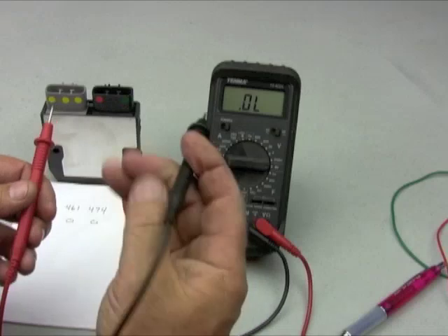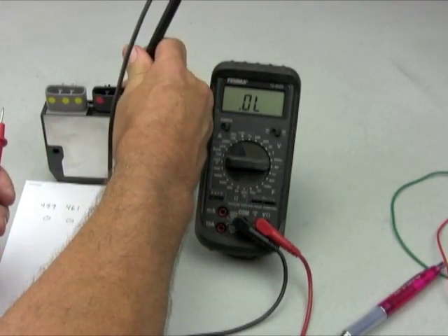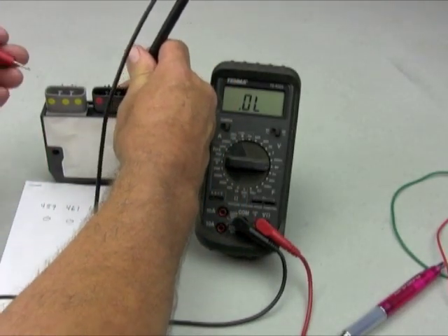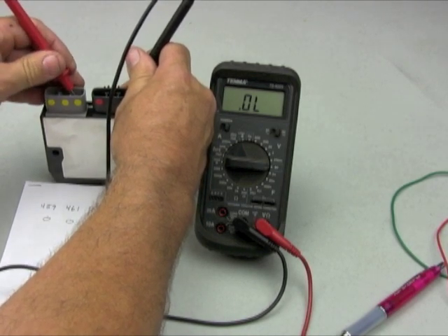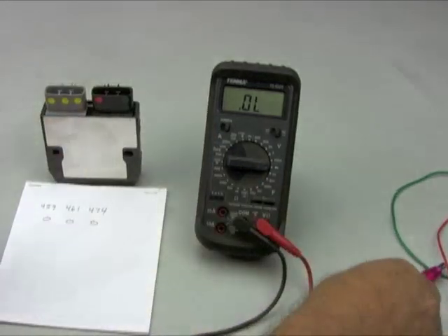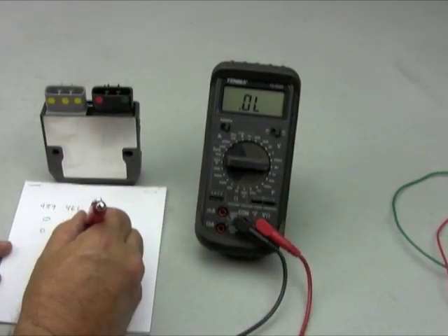Now we're going to take our negative probe, put it on the negative side of the regulator and touch all three of our stator connectors. We have zeros all the way across. Again, that's good.